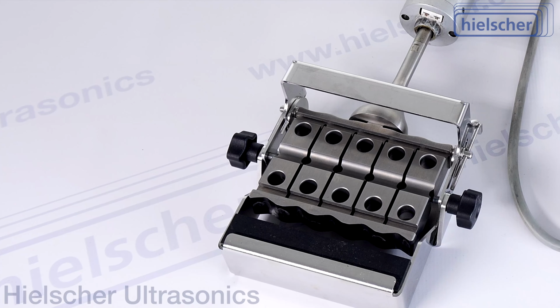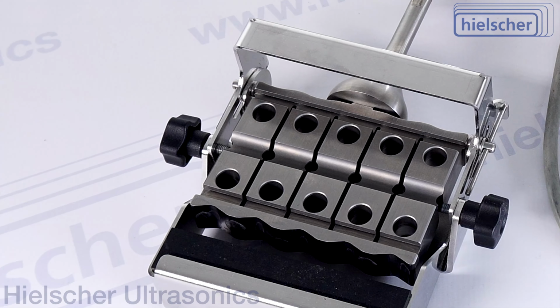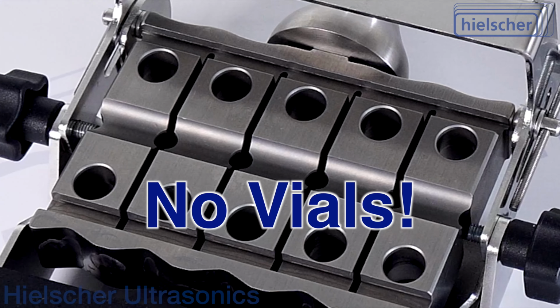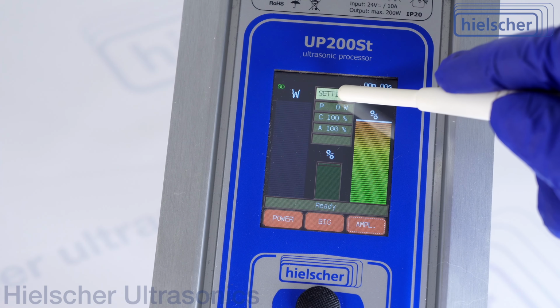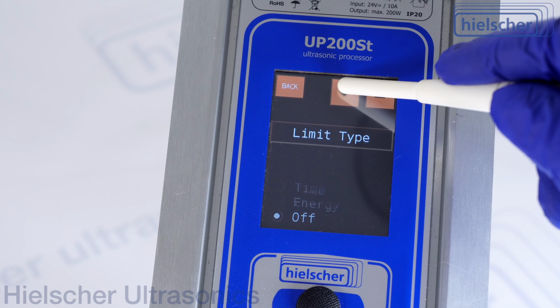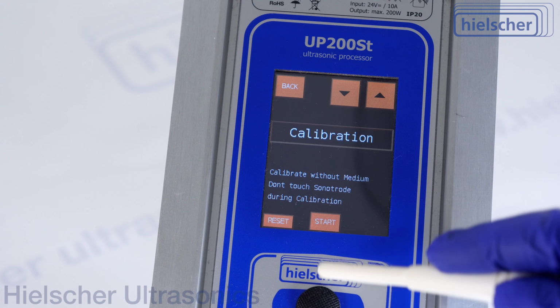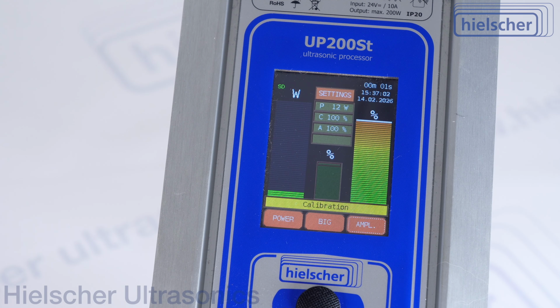Before you start, make sure the VialTweeter sonotrode is tightly mounted. Do not insert any vials. On the touchscreen, open the settings. Scroll to the calibration screen using the arrow buttons. Press Start. The calibration runs automatically. It takes about 25 to 30 seconds.